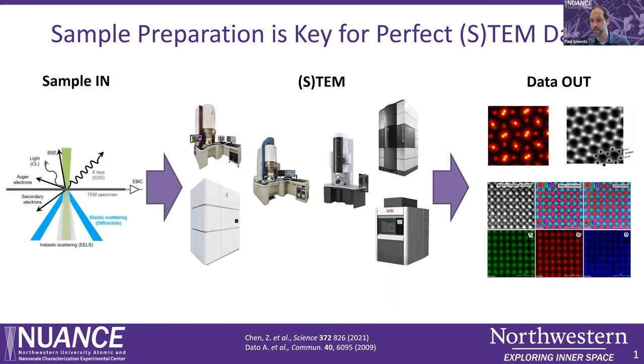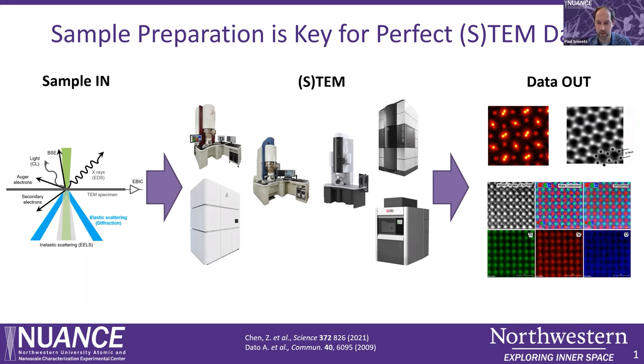What you hear much less often about is really the sample preparation process. On the left-hand side, I show the interactions of a primary beam, shown in green, with a thin TEM specimen. The majority of the electrons need to be transmitted through the sample. Whereas if you have a thicker sample, your probability of electron scattering will increase and multiple scattering effects can take place. The electron mean-free path gets altered depending on conditions like what accelerating voltage you're using.